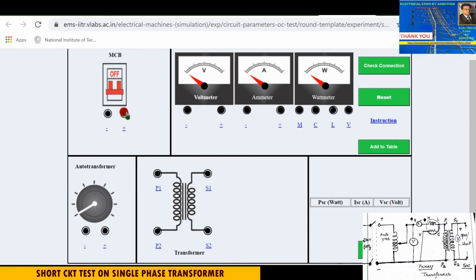So connect the positive of the MCB single phase supply to the positive of the auto transformer, then the negative of the MCB to the negative of the auto transformer. Then this voltmeter is connected across the auto transformer to measure the voltage, positive to positive and negative to negative. So this voltmeter will read the supply voltage. During the short circuit test you must remember that a very small voltage, approximately 10% of the rated voltage, is provided, so that the rated current of the single phase transformer will be shown by this ammeter. Then you have to stop.